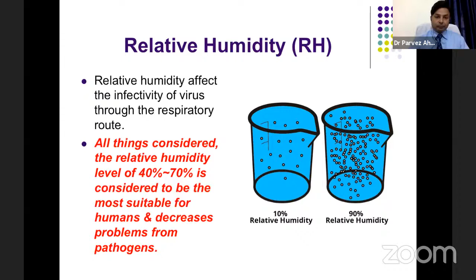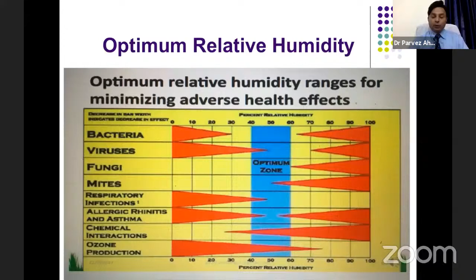This slide is taken from the ASHRAE guidelines. You can see that bacteria, viruses, and fungi are more active at 30 to 40% humidity, and again more active above 70 to 100% humidity. So we get a safe window between 40 to 70%, which is where relative humidity should be maintained in healthcare settings.